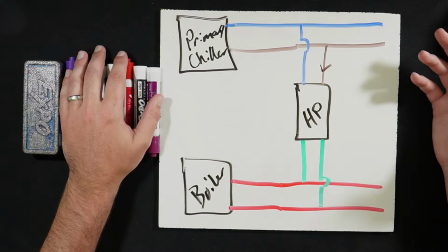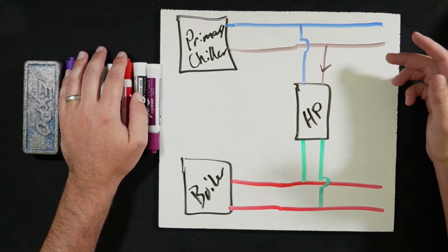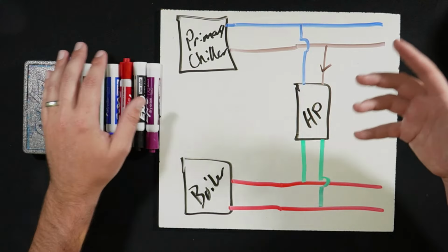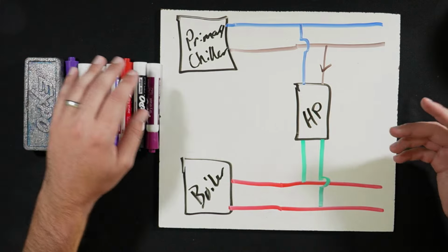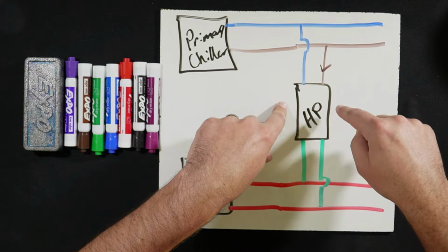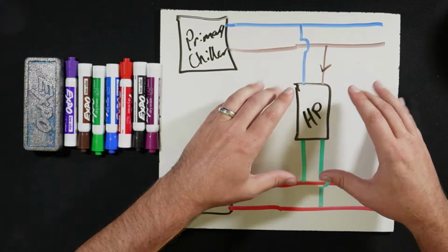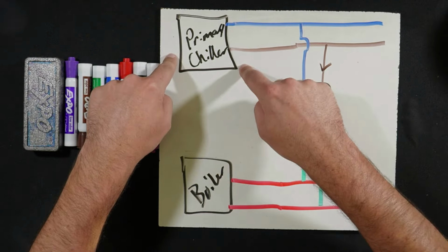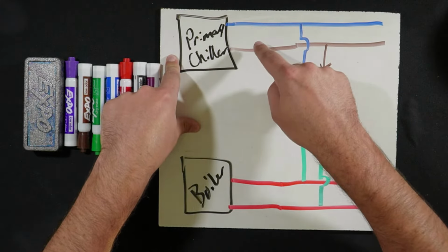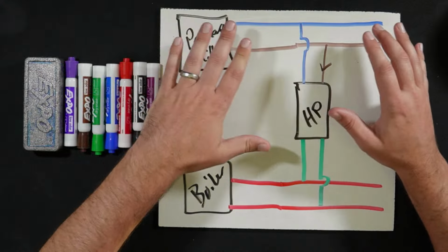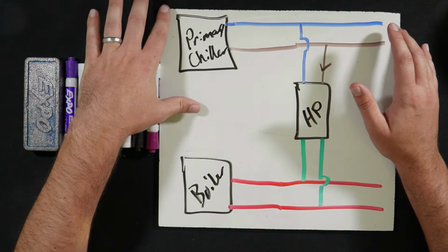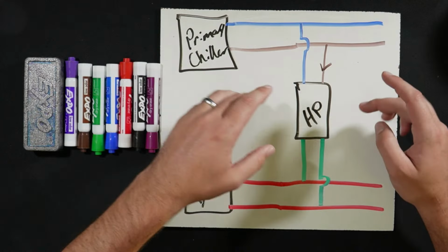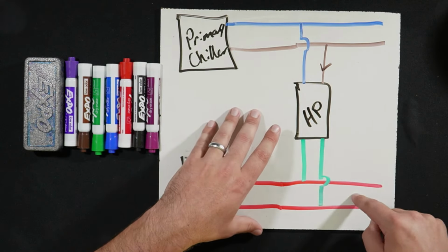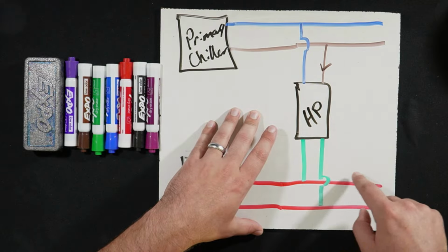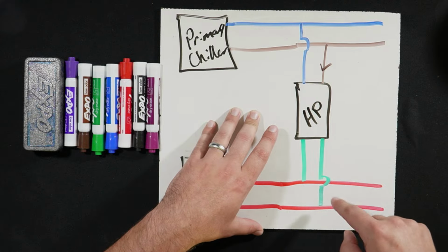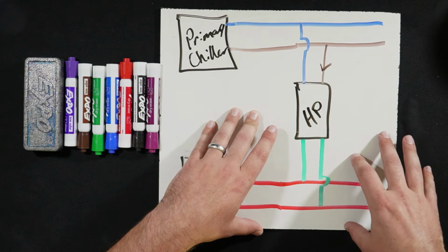Honestly, why call this a heat pump versus heat recovery? In my brain, I think of this as heat recovery, but that's just the way I think about it. Either way, that's what we're doing. So what makes this chiller different from this one? Well, this one is designed to maintain a set leaving water temperature, and it's going to have a lower condenser water temperature compared to what we expect here, because on the condenser side here, we're talking 120, 140 degrees contributing to this hot water loop.